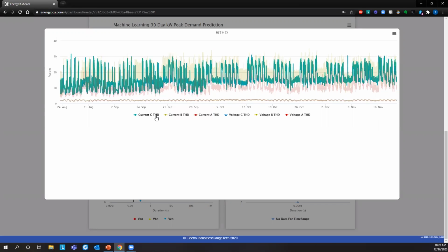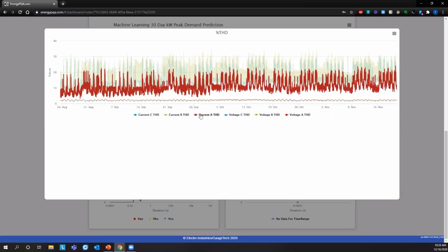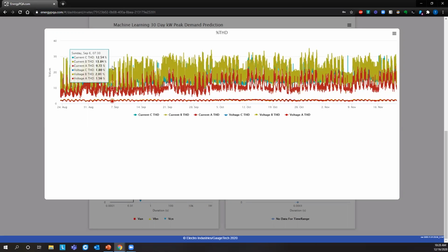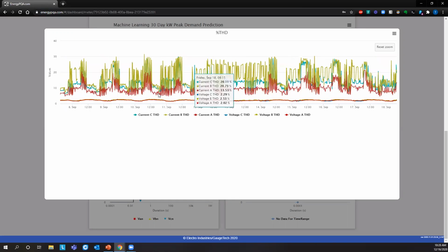So here we have our C phase, B phase, and A phase current total harmonic distortions. You'll notice that these are very high, typically anywhere from 10 to 30%. If we look here, you can see that it's not just at night when a building is typically shut down. It's during the day that we're running that we have higher harmonics. So this would not be an instance of a low load, falsely high harmonics. This is a piece of equipment that we have on our site that is causing these high harmonics.